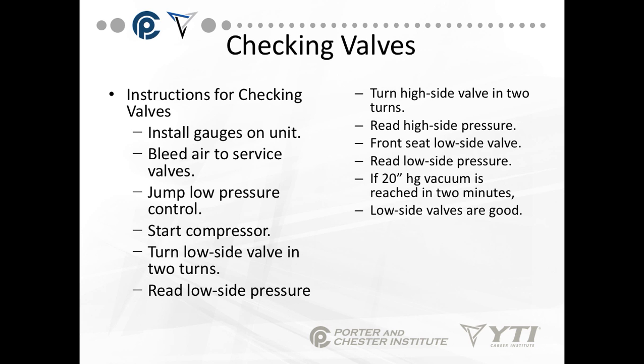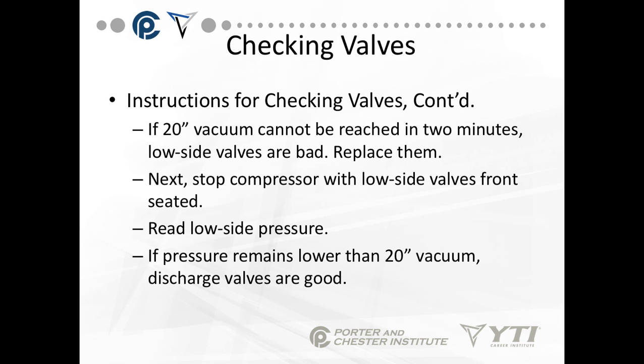To check valves: install the gauges on the unit, bleed the air to the service valves, jump the low-pressure control so the unit doesn't shut off on low pressure, and start the compressor. Turn the low-side valve in by two turns and read the low-side pressure, then turn the high-side valve in by two turns and read the high-side pressure — you've now opened your service valves to mid-seat. Next, front-seat the low-side service valve (all the way in) and read the low-side pressure. You want to reach 20 inches of mercury in less than two minutes — if you achieve this, the low-side valves are good. We want to pull the system into a vacuum, but don't let it run in a vacuum for very long. If a 20-inch vacuum cannot be reached in two minutes, low-side valves are bad and you'll end up replacing the valves (if semi-hermetic) or replacing the compressor.